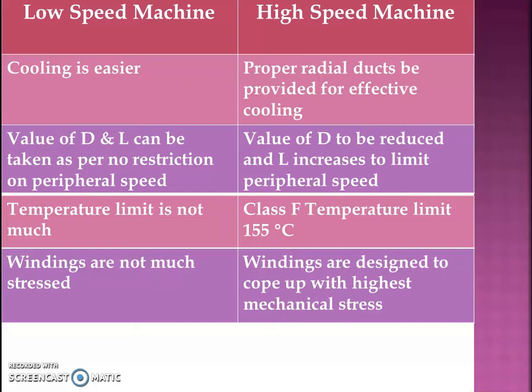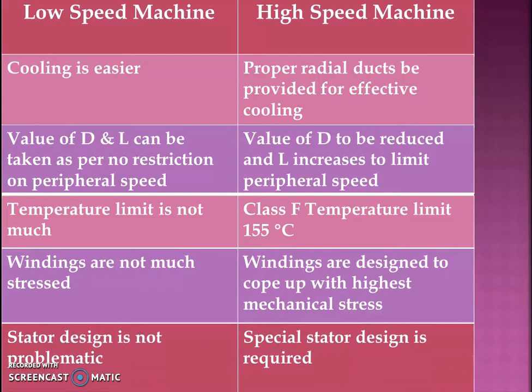These are design differences to take care of when designing low speed as well as high speed machines. In case of a low speed machine, stator design is not problematic — it is simple. While in case of a high speed machine, special stator design is required. Vacuum impregnation and special epoxy resin are used for the stator in high speed machines.